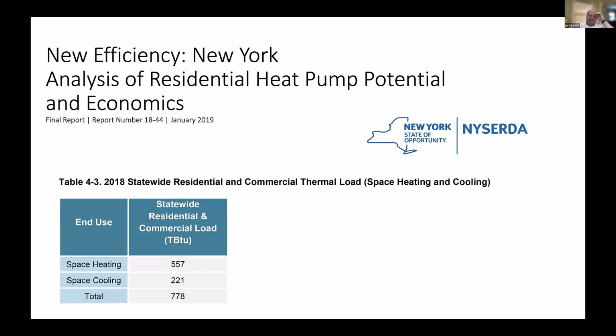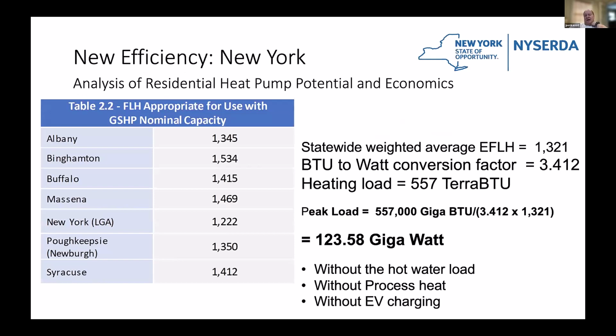How much is that in peak? This is actually the building use, not the fossil fuel amount of heat going in - this is the building load itself. You can convert that by looking at the full load hours, published by NY-GEO. And again, the 557 tera-BTUs is also a published number by NY-GEO, which they have estimated. You can calculate the peak usage by matching it with weather data and looking at the full load hours. The weighted average full load hours is about 1,300 in New York State, and that equals 123 gigawatts.